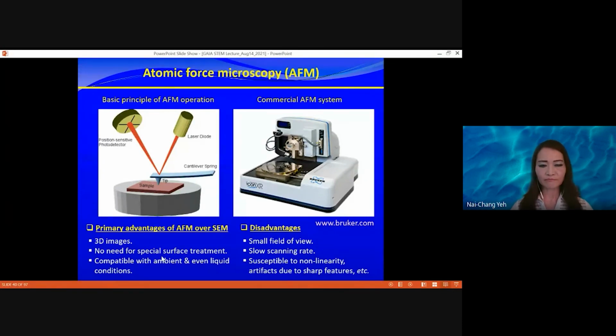Also, you don't need to do very special surface treatment. Unlike scanning electron microscopy, where you have to clean your surface and do all kinds of preparation in advance, with AFM you can even work in ambient environment or liquid, whereas SEM needs extremely high vacuum. But the disadvantage is that it's a slow process, the field of view you can scan is limited, and if you have very dramatic variations or very sharp features, you won't be able to detect them.